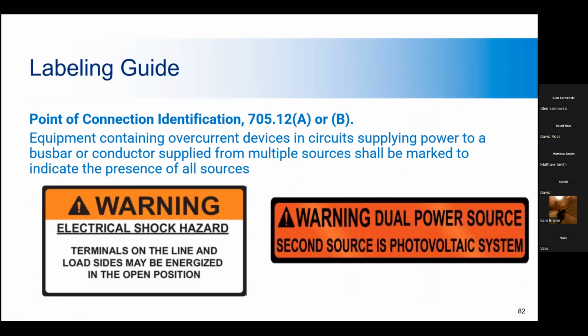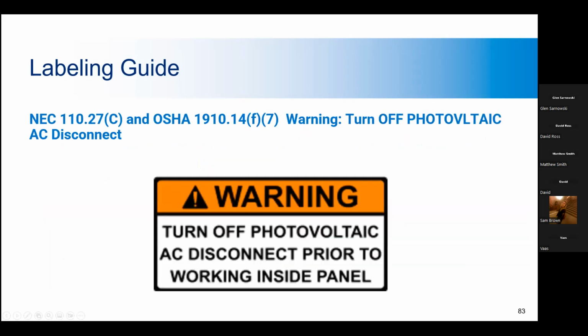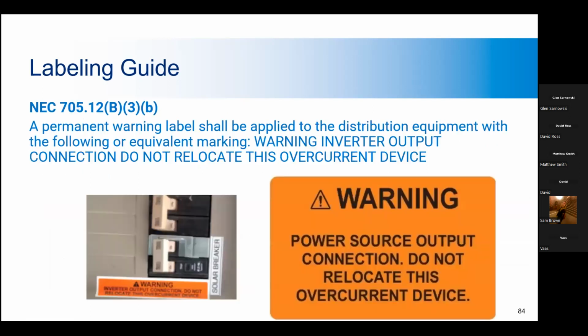At the point of interconnection, you need to identify all sources of power being supplied to the bus bar or the conductor, and label it that shutting down one disconnect doesn't necessarily shut down the whole system. And this may be the first indication for someone working on the system that PV is installed on a building. This is another label required by NEC and OSHA. It's a pretty self-explanatory one. Just like the other ones, you need to make sure all the disconnects are open before working in a panel to avoid it being energized while you're working on it.